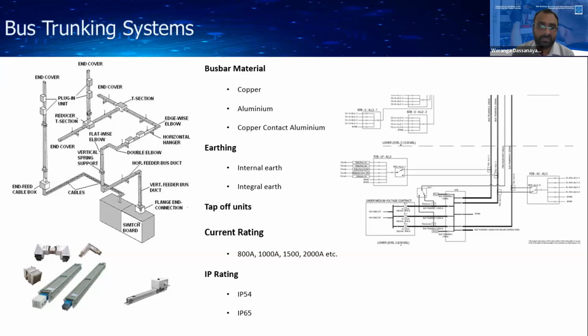To take power out from the busway system, you use a tap-off unit. That means these tap-off units tap the conductors inside the busway system and give you a termination point. If you want to take power out from this busway system, you have to use a tap-off unit. The current ratings of busways are available in 800, 1000, 1500, 2000 amps, etc. And there are also different types of IP ratings available, IP54 and IP65.